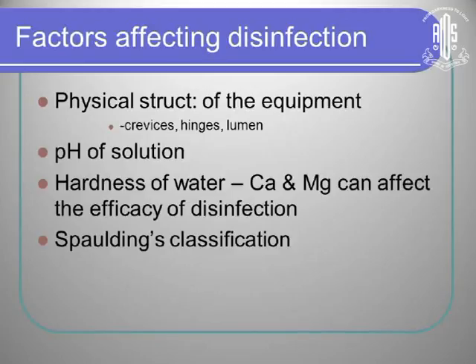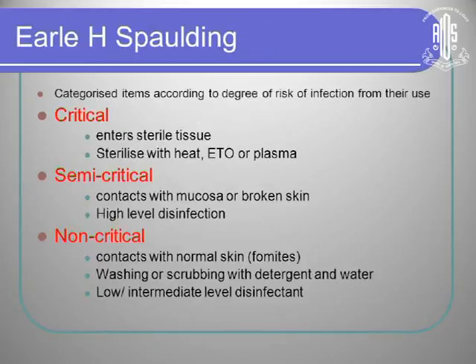The pH of the solution — glutaraldehyde is active in an alkaline pH. Hardness of water is also a factor. Most important is the Spaulding classification, which determines how to disinfect items. For example, whether to disinfect a stethoscope or OT footwear is determined by this classification. All items in a hospital are categorized according to the degree of risk of infection from their use.